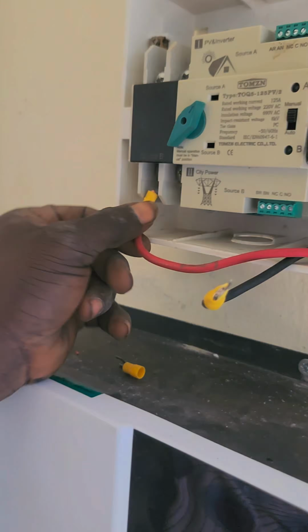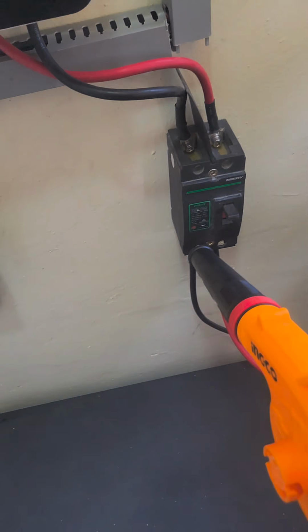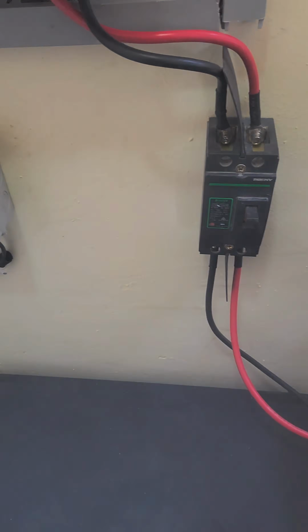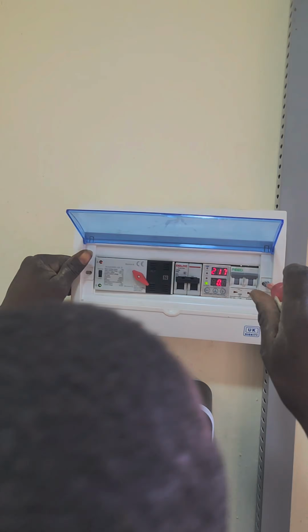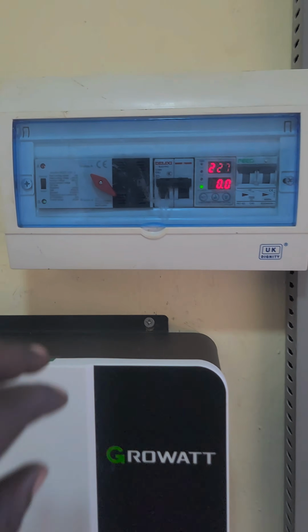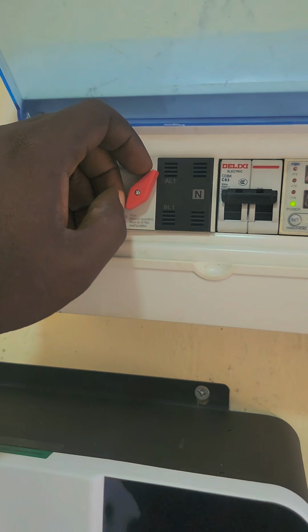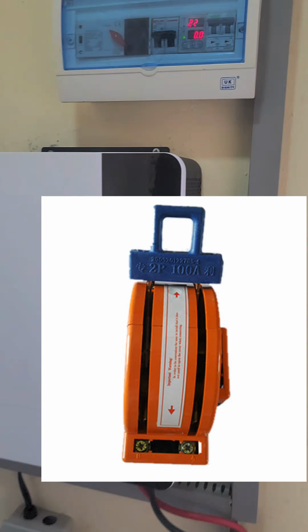At this part the electrician came in to do some work, and I added a blower to just blow out dust from the system. The electrician finalized the work, and the inverter is up and running. The house is powered. I use a changeover switch and ATS, which is much better than the knife switch that a lot of people use.